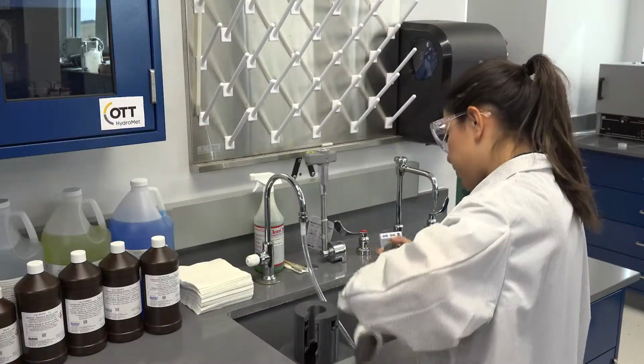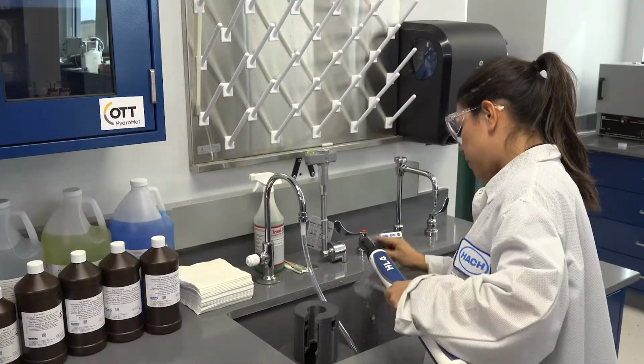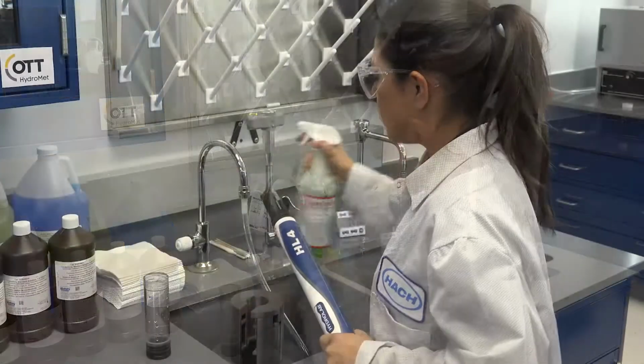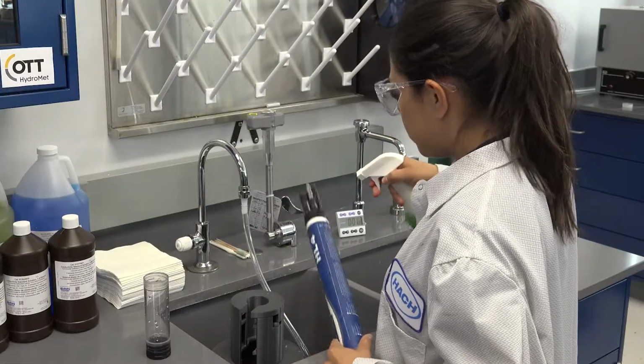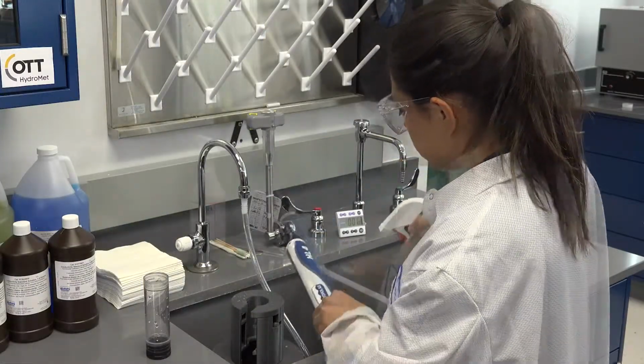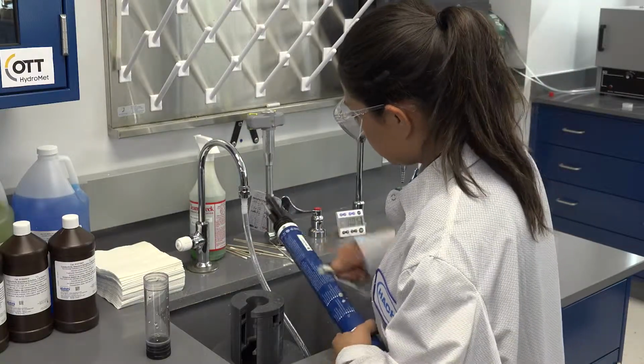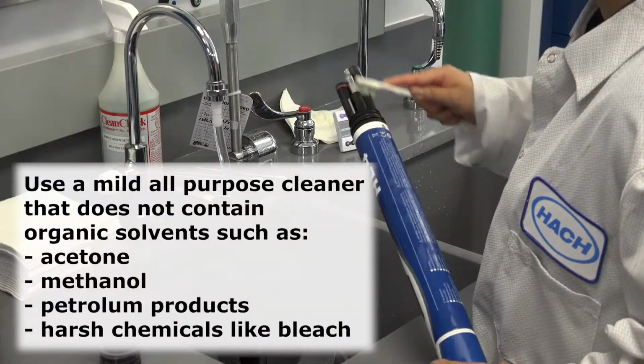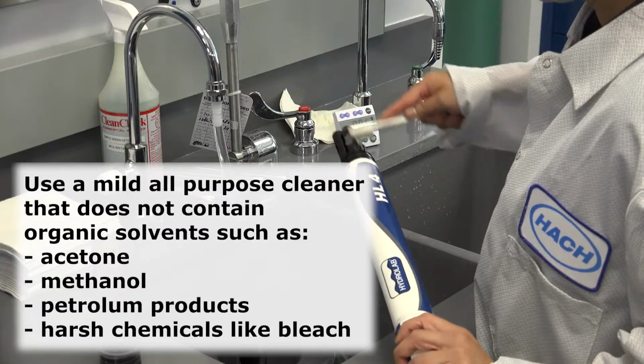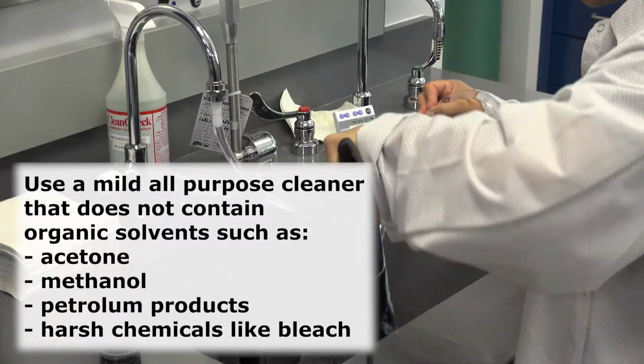The LDO probe is nearly maintenance-free. To ensure accurate readings and long sensor life, the probe should be kept clean. After each deployment, the sensor should be cleaned with a cotton swab or soft brush in soapy water to remove any oils or organisms. Organisms living on the sensor may consume or produce oxygen and change the readings.